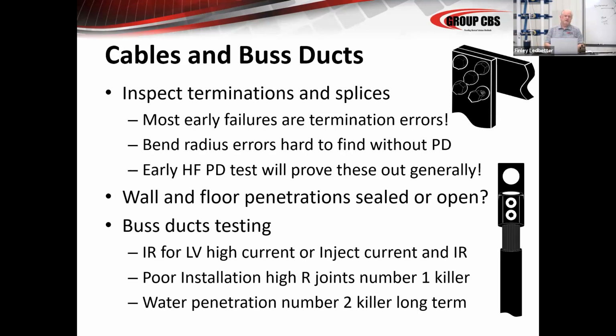In bus duct testing, obviously, in the lower voltages, IR is a very good test. And in the higher voltages, you've got to go with PD to really do any good. High resistance joints are the number one killer in bus ducts. A lot of bus duct today is not bolted joints that are torque wrenched. They're simply break-off connections. Make sure that all that stuff is installed correctly. You can pass current through it, and then you can IR test it. You can take the two ends, loop it together, A to B, B to C, and then run current through the whole system. And if it's a 1200 amp bus duct, you can put 1200 amps on it at low voltage, IR scan it. There's lots of ways to get that. Always look for possible water penetration, as that's a very big killer.